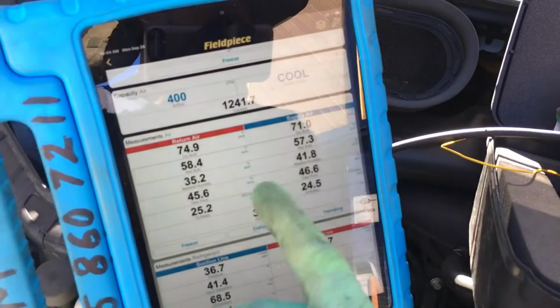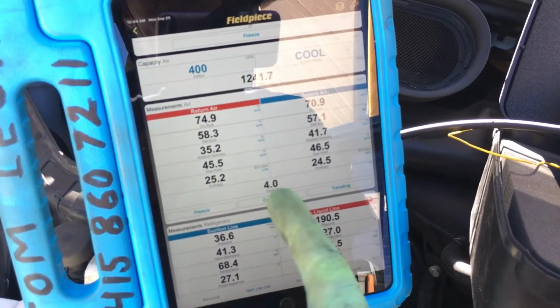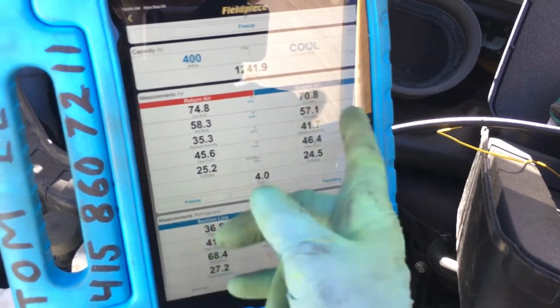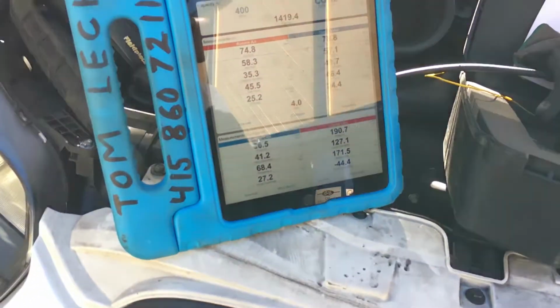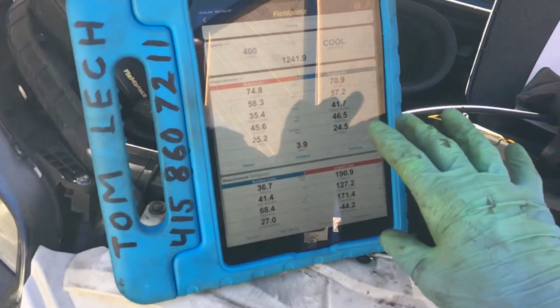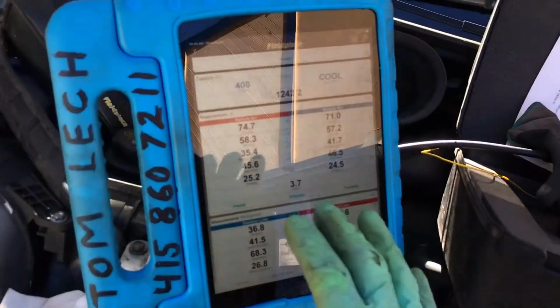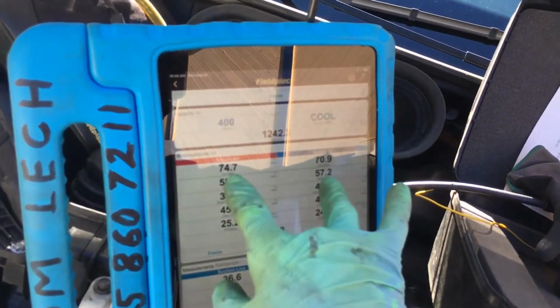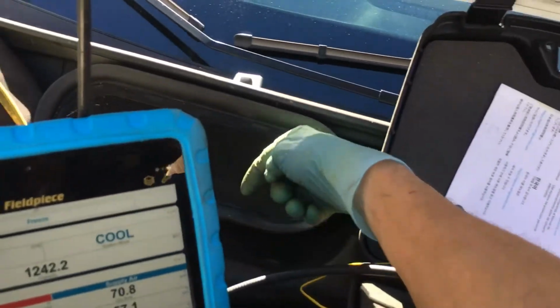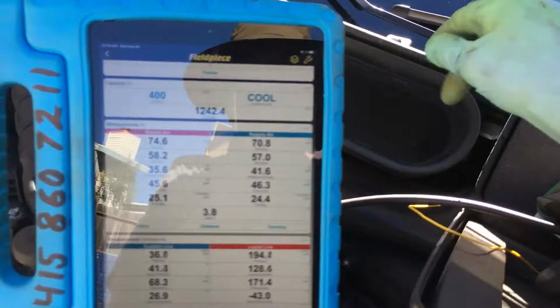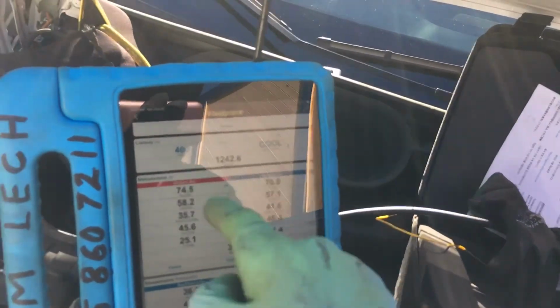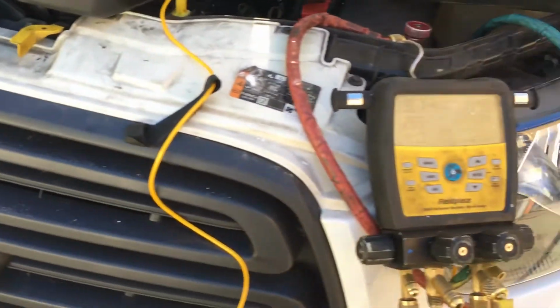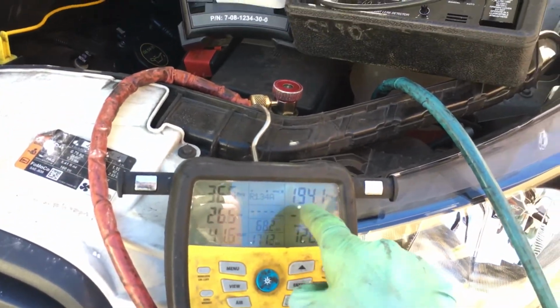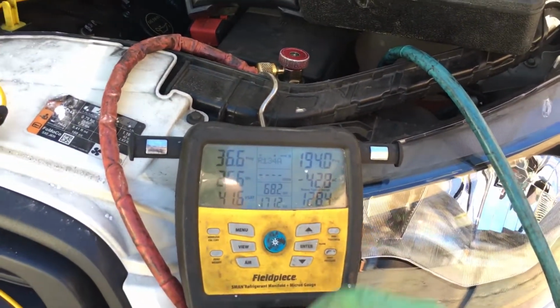So, where was I before I got distracted calling my tool off? Now I've got to get a different one, because I cannot be 4 degrees off. That's not allowed. But just for testing purposes, this is the air temperature going over my evaporator right now. Remember, we were doing external air from the engine at 115 degrees going over the evaporator. So let's average these out and say we have 72 degrees going over the evaporator, but we still have 194 psi on the high side.